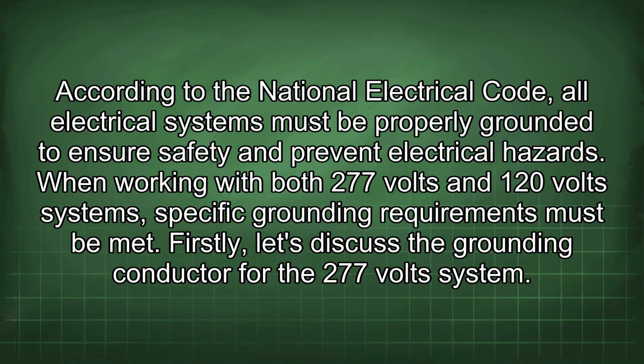According to the National Electrical Code, all electrical systems must be properly grounded to ensure safety and prevent electrical hazards. When working with both 277 volt and 120 volt systems, specific grounding requirements must be met. Firstly, let's discuss the grounding conductor for the 277 volt system.